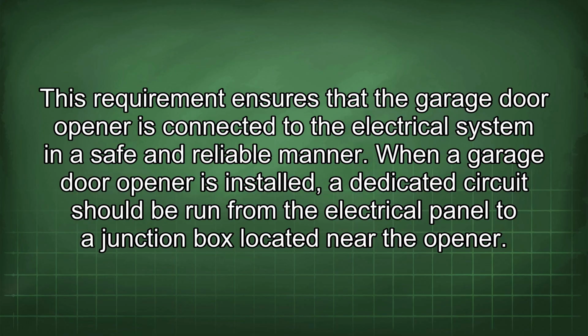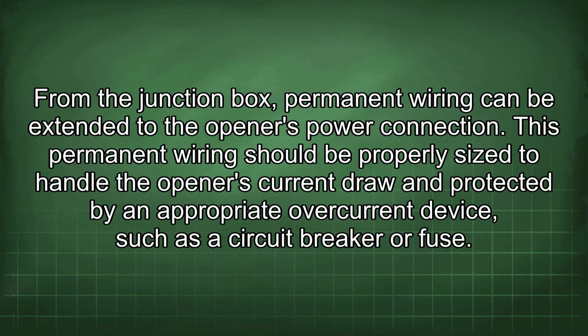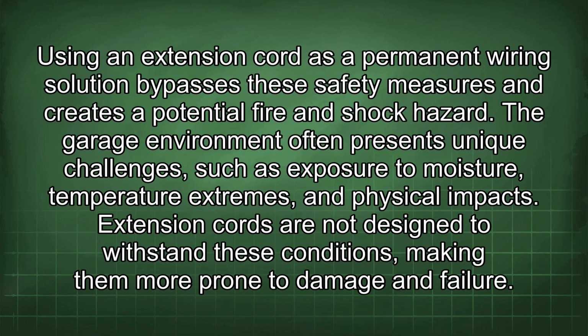When a garage door opener is installed, a dedicated circuit should be run from the electrical panel to a junction box located near the opener. From the junction box, permanent wiring can be extended to the opener's power connection. This permanent wiring should be properly sized to handle the opener's current draw and protected by an appropriate overcurrent device, such as a circuit breaker or fuse. Using an extension cord as a permanent wiring solution bypasses these safety measures and creates a potential fire and shock hazard.